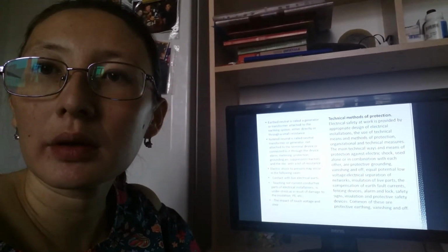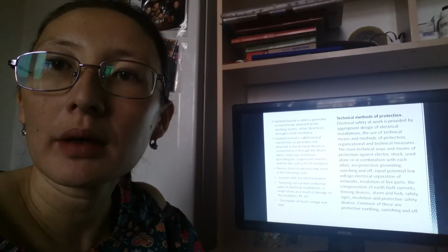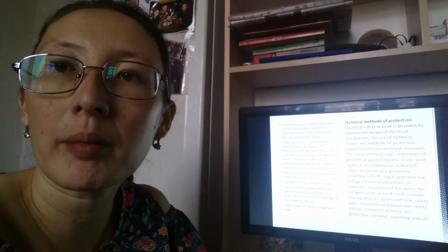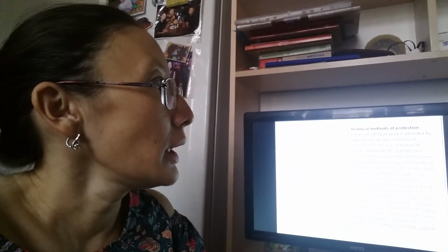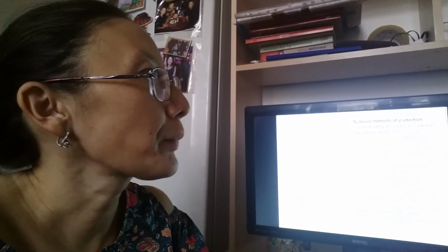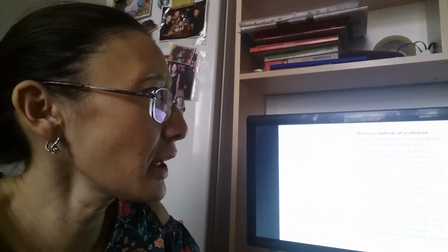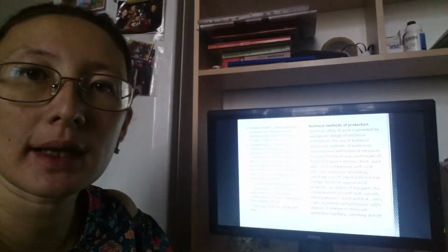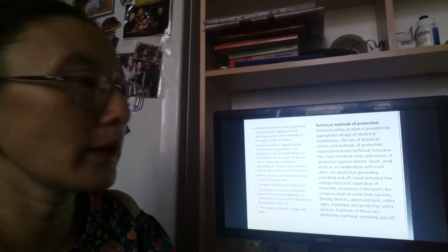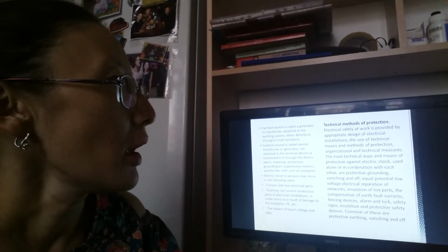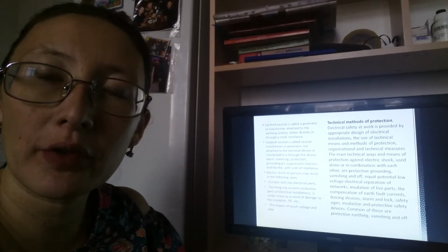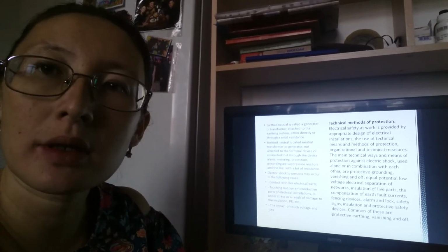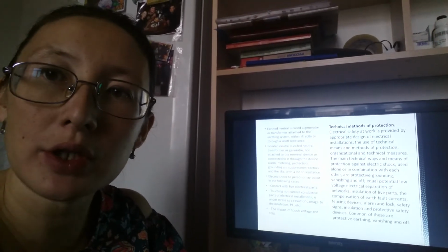So the grounding system will be a kind of technical protection from electric shock. Electrical safety at work is provided by appropriate design of electrical installations, the use of technical means and methods of protection, and organizational and technical measures. The main technical ways and means of protection against electric shock, used alone or in combination with each other, include protective grounding, zeroing, and automatic shutdown systems.